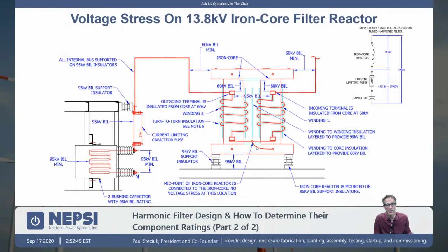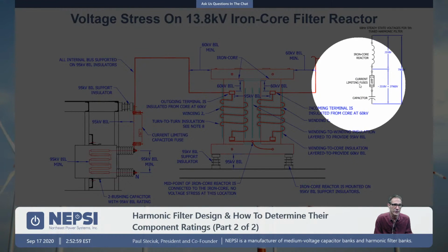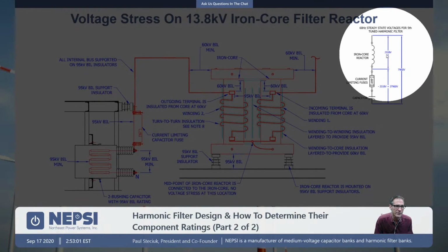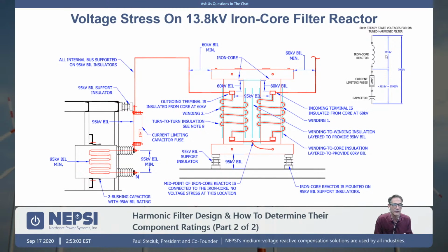And you can have a similar diagram for 34.5 kV systems, where the BIL might be 150 or 200 kV BIL. But the key here is for single-phase reactors, up here I think we're showing about 318 volts across the reactor itself. So there's not a whole lot of voltage there. So basically low voltage on the winding, so it's very reliable from an impulse and voltage withstand point of view.